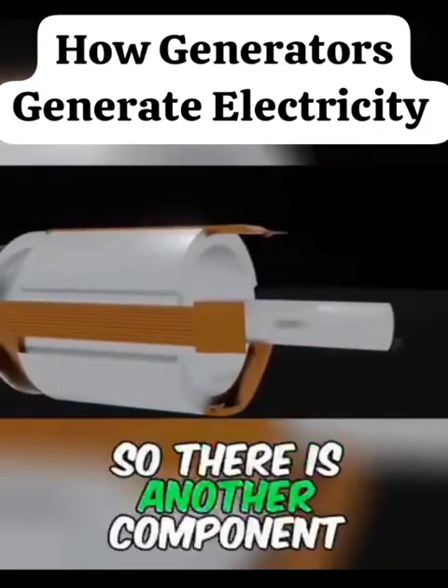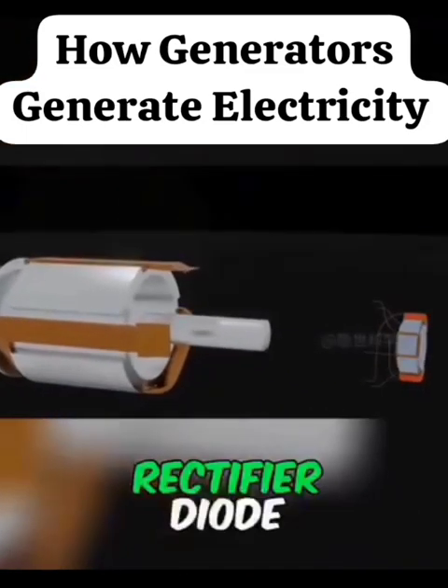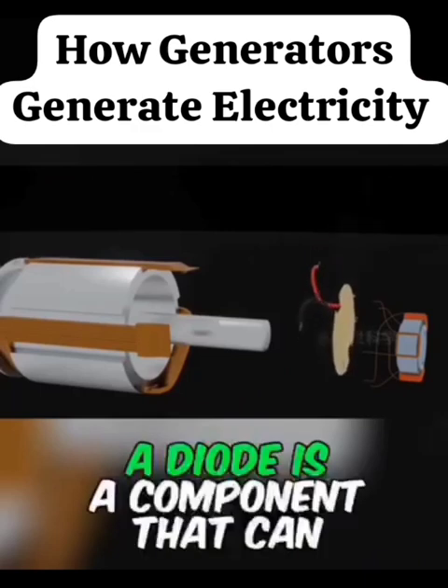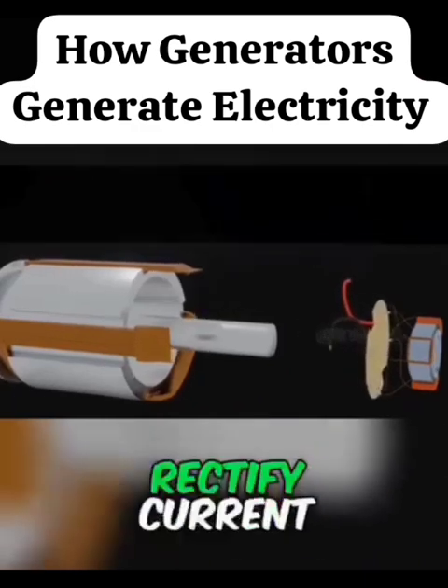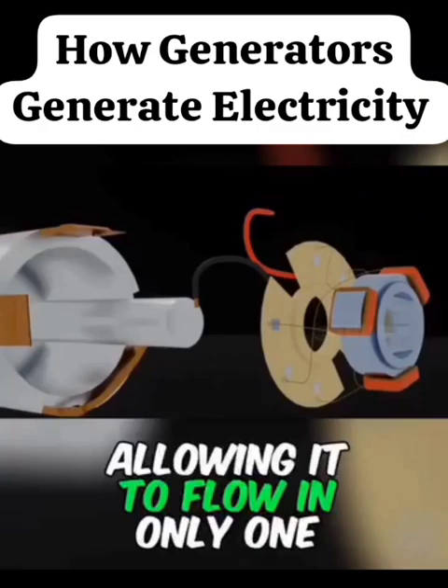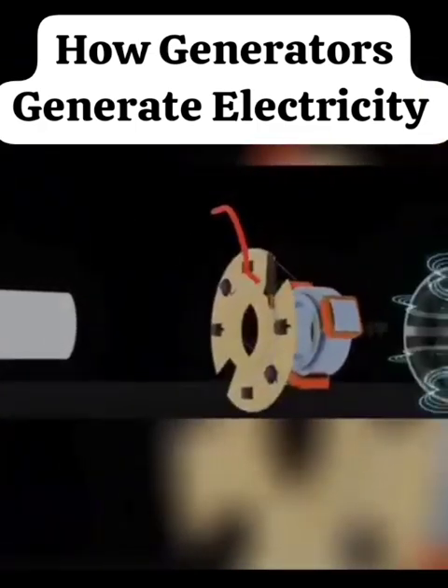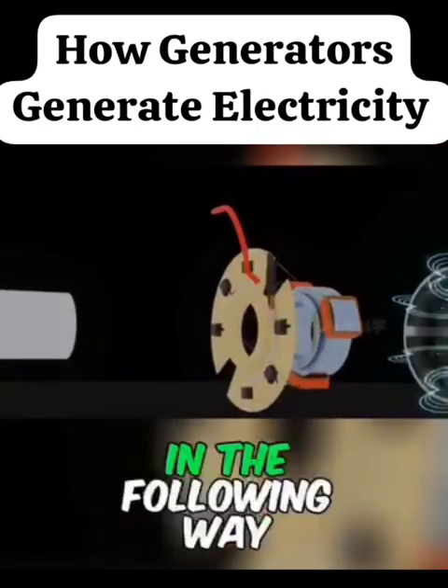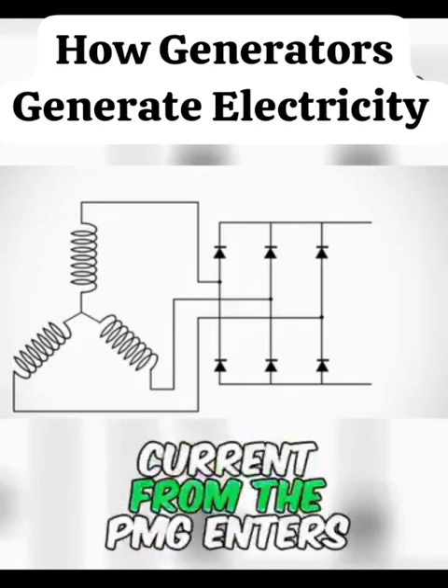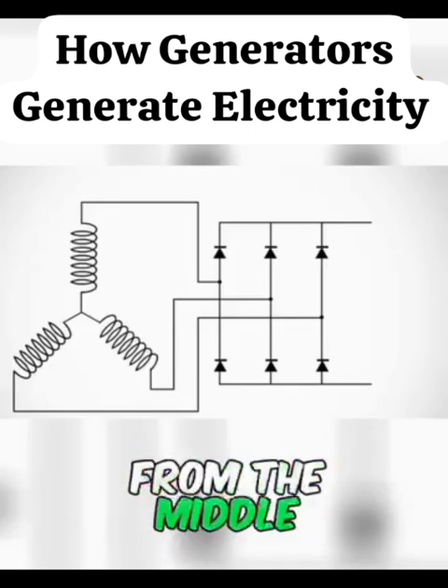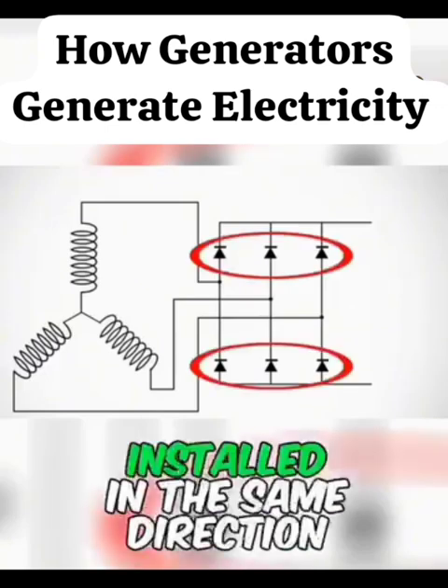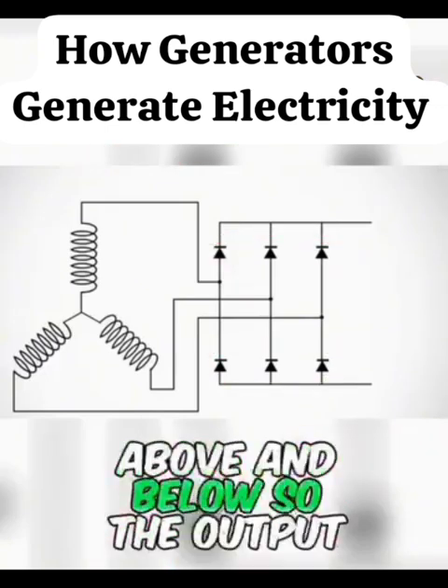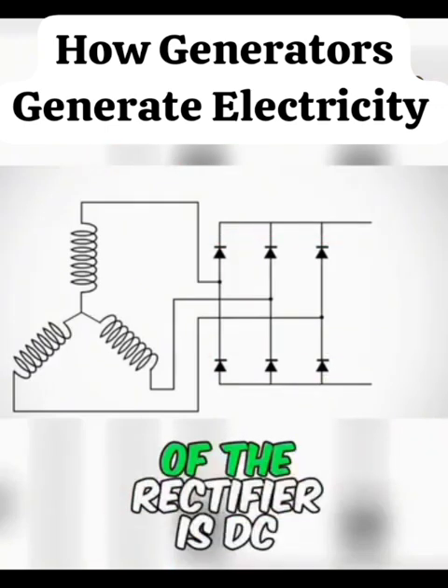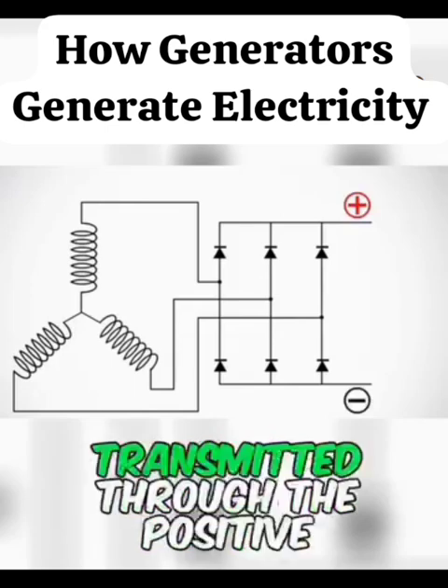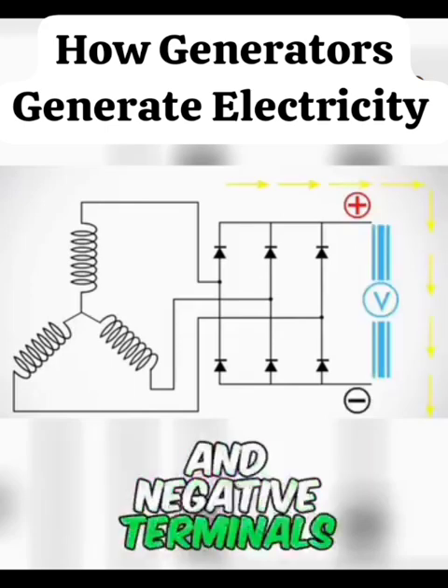So there is another component. Rectifier diode. A diode is a component that can rectify current, allowing it to flow in only one direction. The diodes used are connected in the following way. Current from the PMG enters from the middle, with several diodes installed in the same direction above and below. So the output of the rectifier is DC transmitted through the positive and negative terminals.